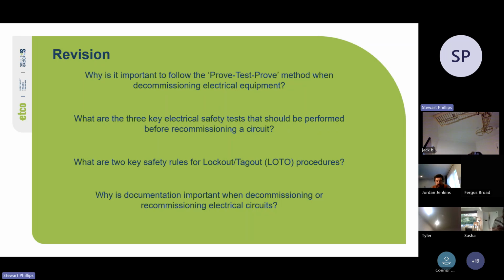So, three key electrical safety tests you should perform before recommissioning a circuit: your insulation resistance test, your earth continuity test, and your polarity test. You always need to do your IR test, earth continuity, and polarity. If you don't do any other tests, you should always do those three.